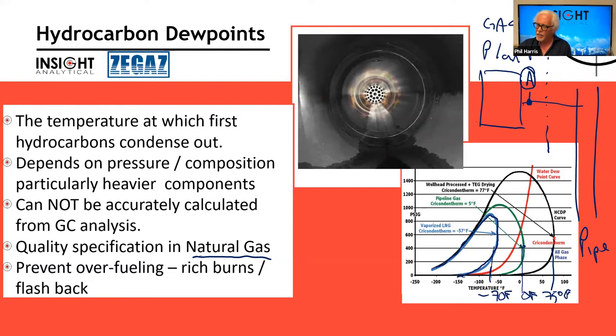Well, the gas plant can put in an analyzer that doesn't do it very well. The gas plant may say, well, I'm going to put an analyzer in there. The question is, are they going to use a technology that's going to work well? And so if they're doing it by a gas chromatograph, as I said, they may not actually get an accurate number.